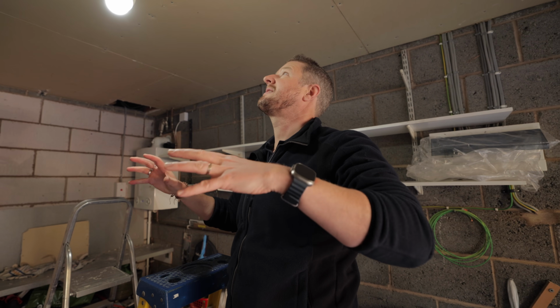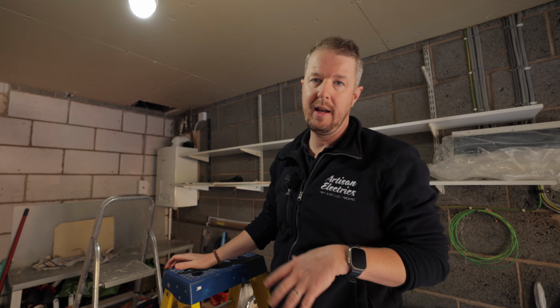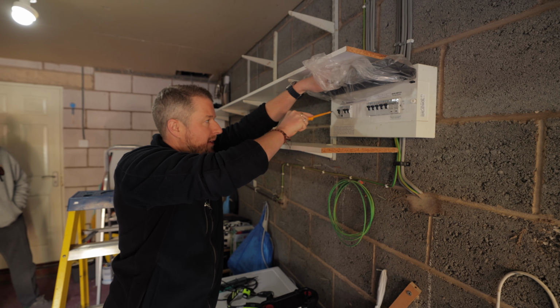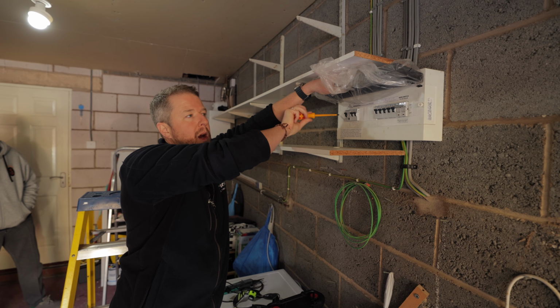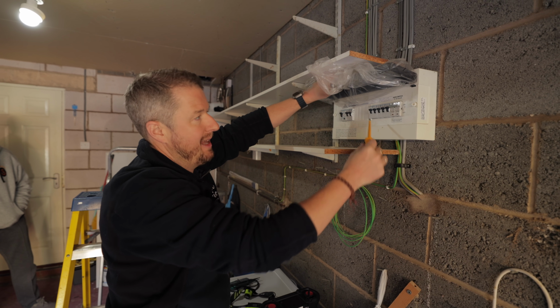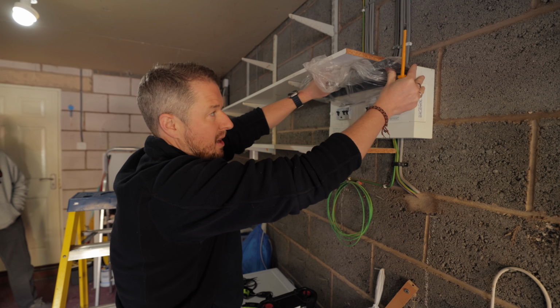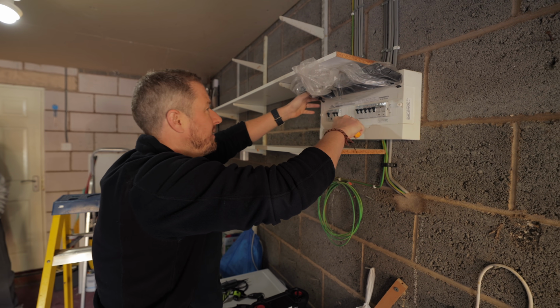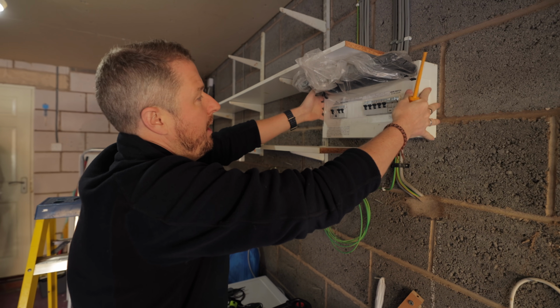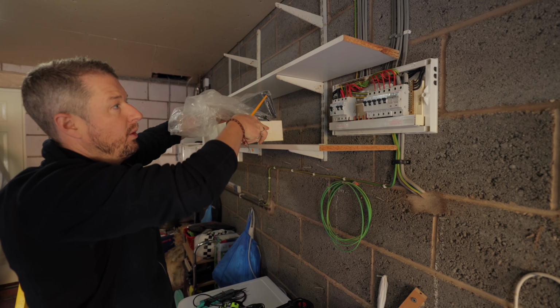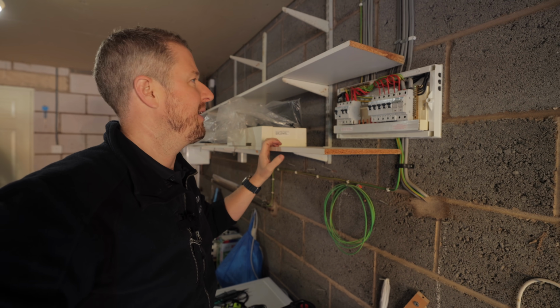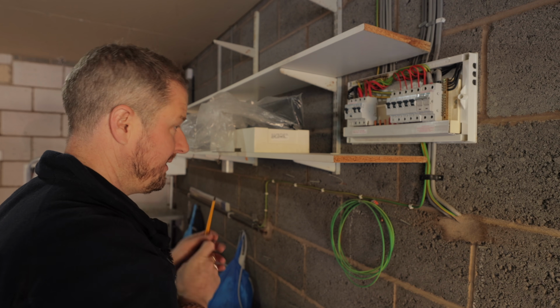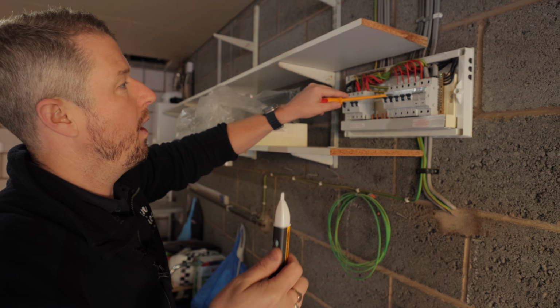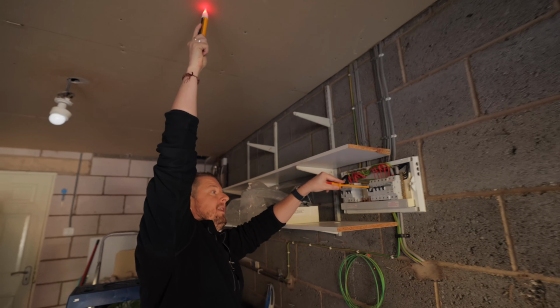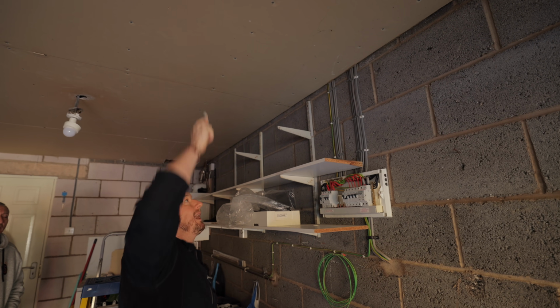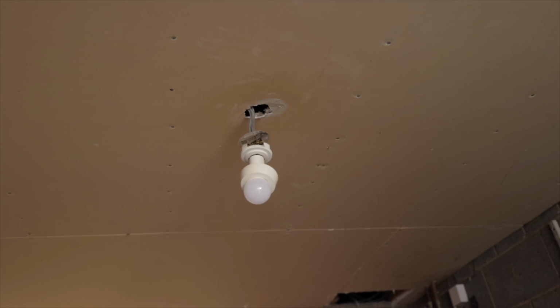We'll put some power into the circuit and see if there are any short circuits within the cabling. You might wonder, well, if there is some earth leakage on this circuit, why is it not tripping? And the reason is that the lighting circuits are not protected by an RCD. Only the sockets, I think, and the shower are protected by an RCD, because this is quite an old consumer unit. Oh wow, check that out. That's actually very nice and neat. The first thing we'll check is, when we turn it off, does the electricity on the ceiling go off? And it does. So it's clearly something with this lighting circuit for the downstairs.